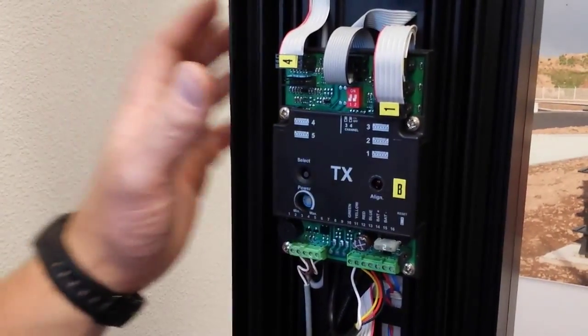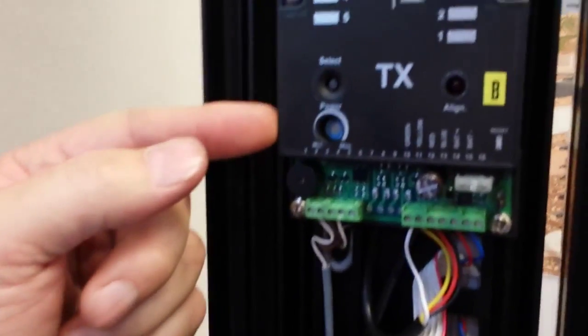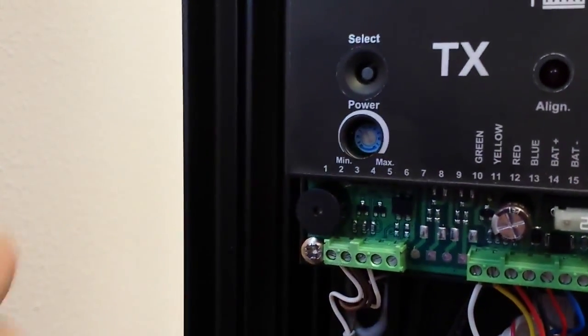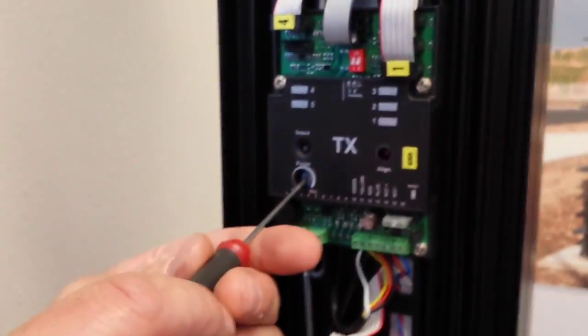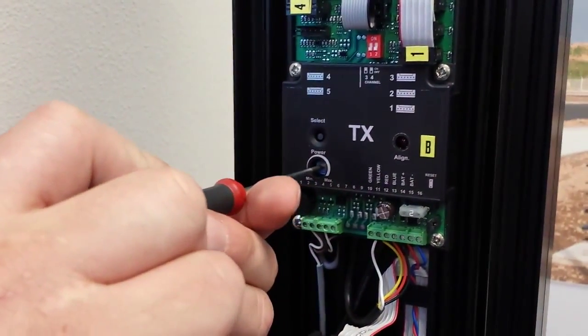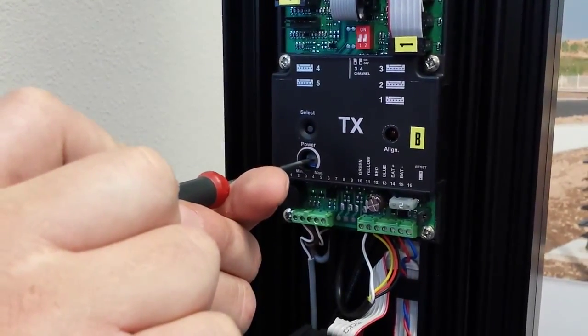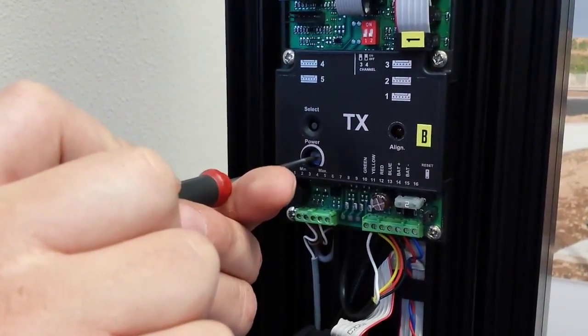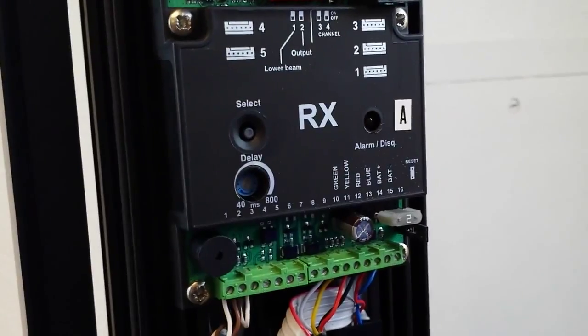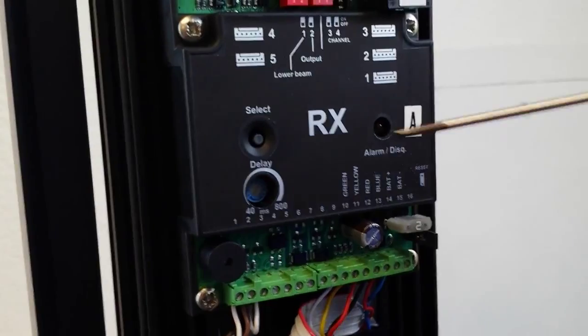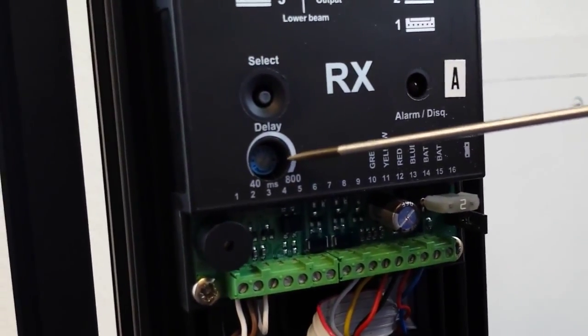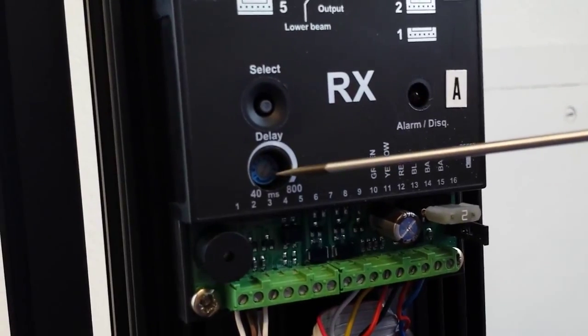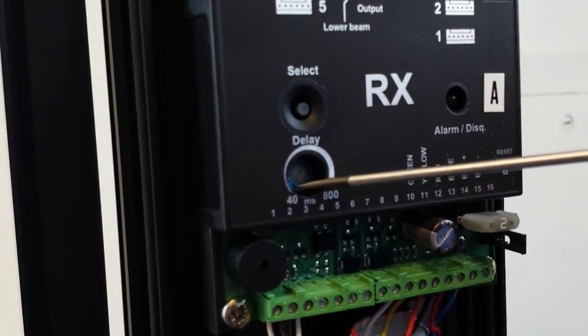After you're done aligning on the TX side, there is a potentiometer for power. What you want to do while still in alignment mode is you want to turn that potentiometer down to where you lose your solid tone, and then just back it back up until you get that solid tone again and let it set. On the RX side, the potentiometer is a delay, it's not power. Do not adjust this one. If you adjust the delay up on this, you'll be able to walk through the beam without causing an alarm.